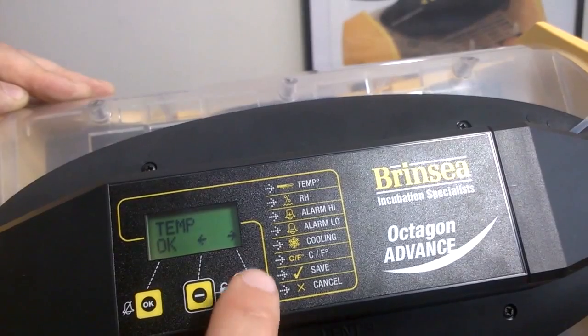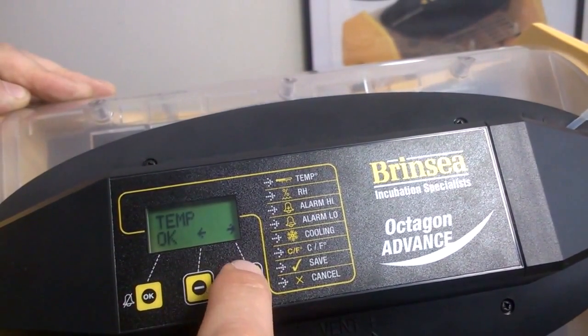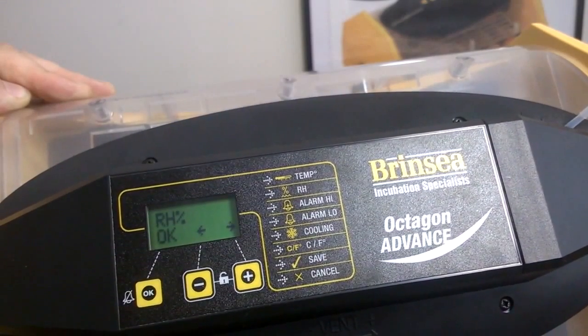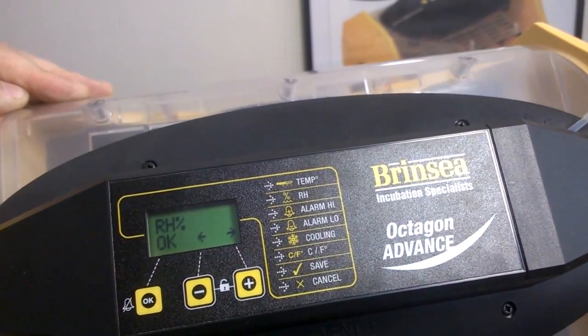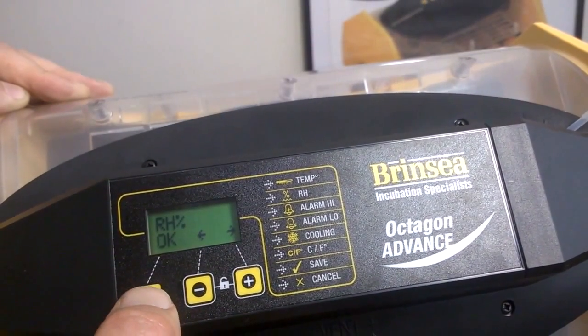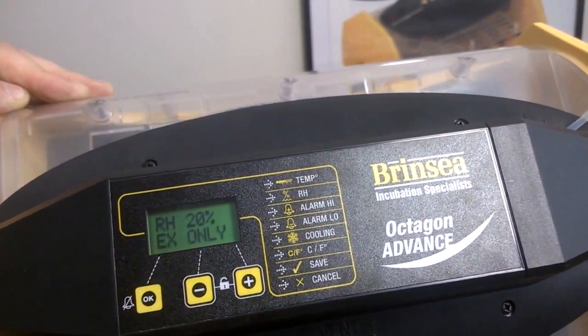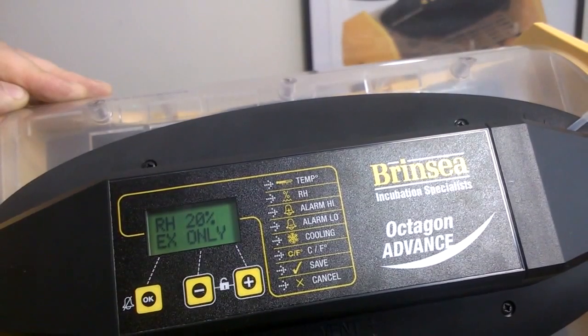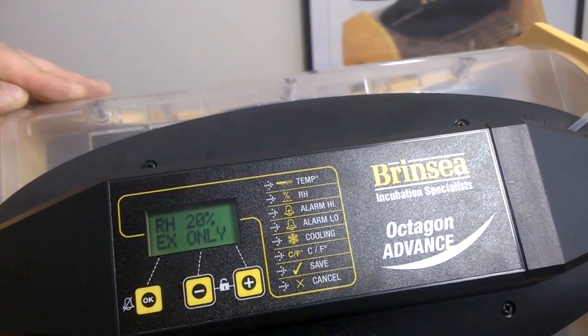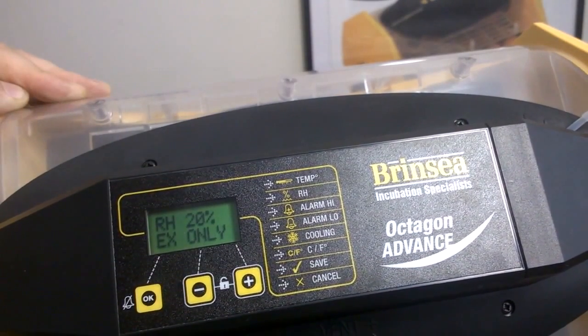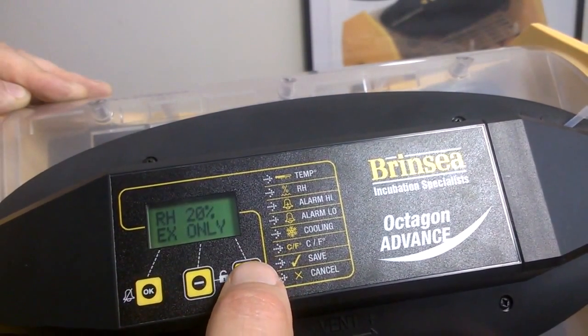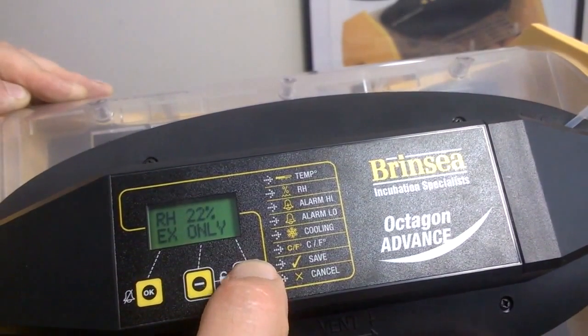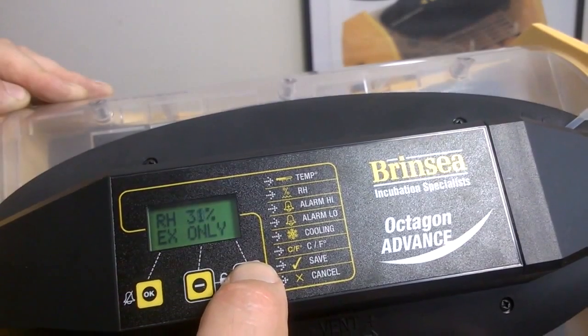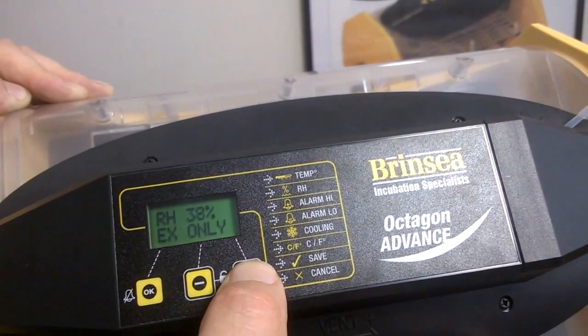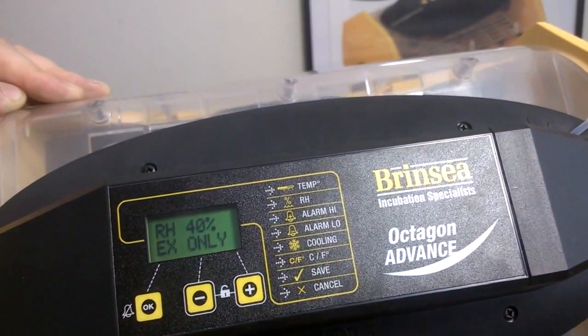So I'm going to press the plus key down to take me on to the next setting. Didn't press it down properly. There we are. That's taken me to my next setting, which is relative humidity, which I do want to look at. I want to enter that setting and see what it's set at now. So I press OK on that to go into the setting. And there we are. It tells me it's relative humidity 20%, and that I can only set the humidity when I'm using the pump. So with the pump, I can now add humidity. I'm going to take that up to 40%. There we are. So I'm going to go for 40%.